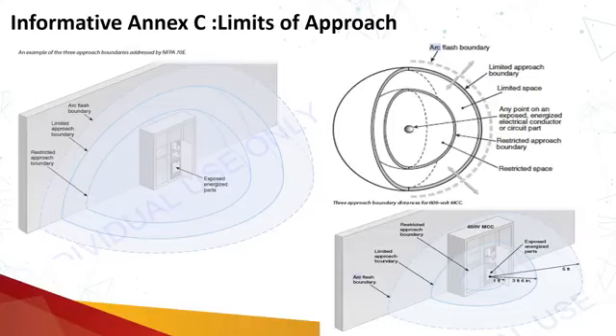Using RTU, they performed the operation. That ring main unit was an oil filled RMU. A blast happened inside that ring main unit, maybe due to some maintenance issue or other problems, and the oil spilled and it resulted in burn injury to the people who were standing at a considerable distance. So they did not take into consideration that flashover could occur in this newly maintained equipment, and that there was a risk of burns due to the hot oil. So if you are performing operations remotely, then these boundaries will be there. Okay.